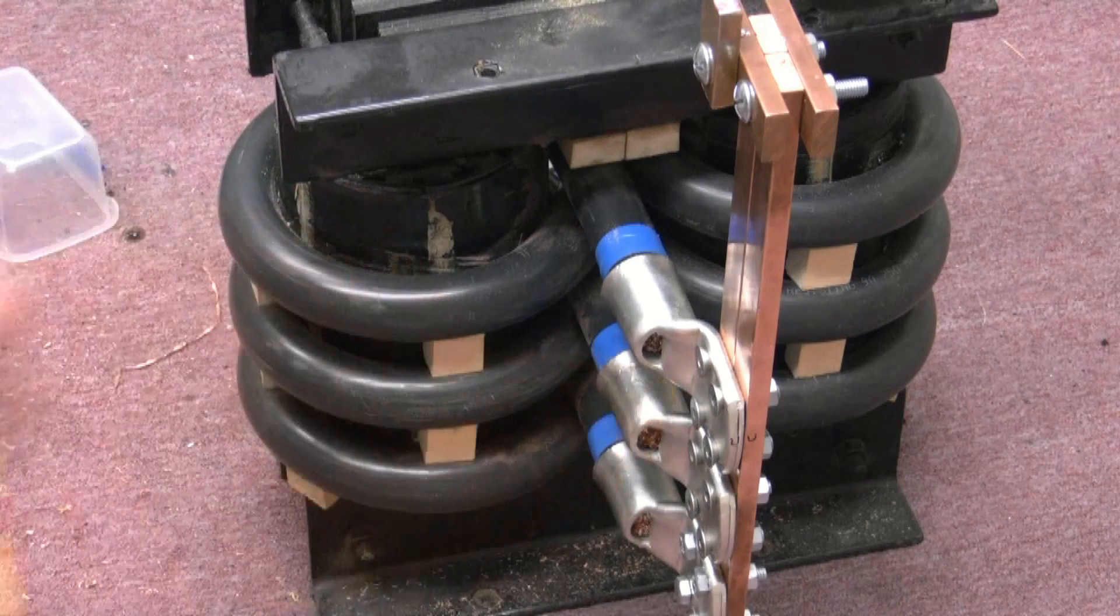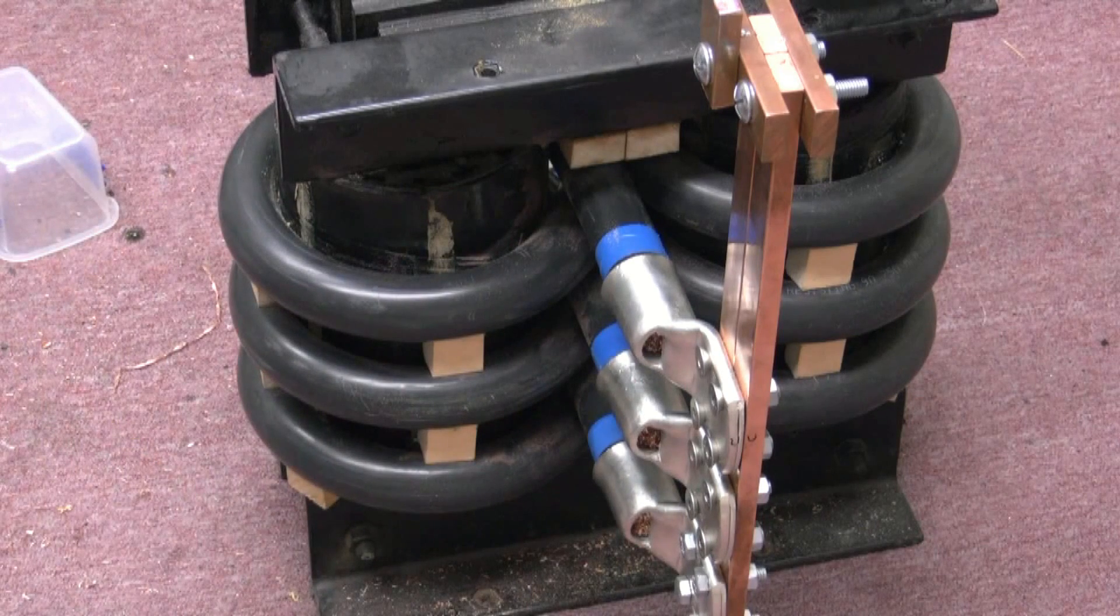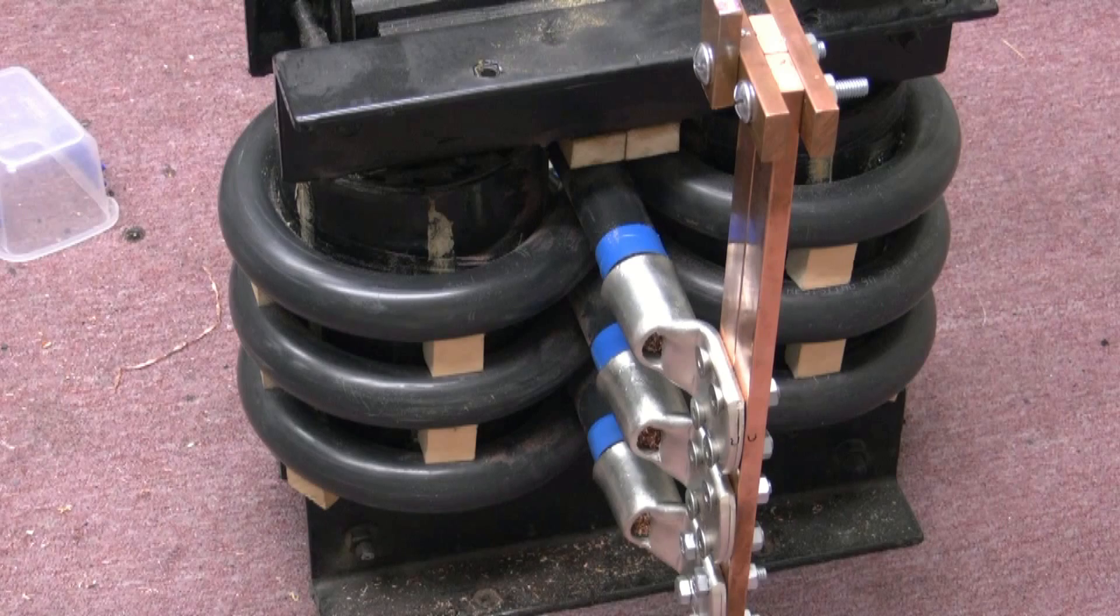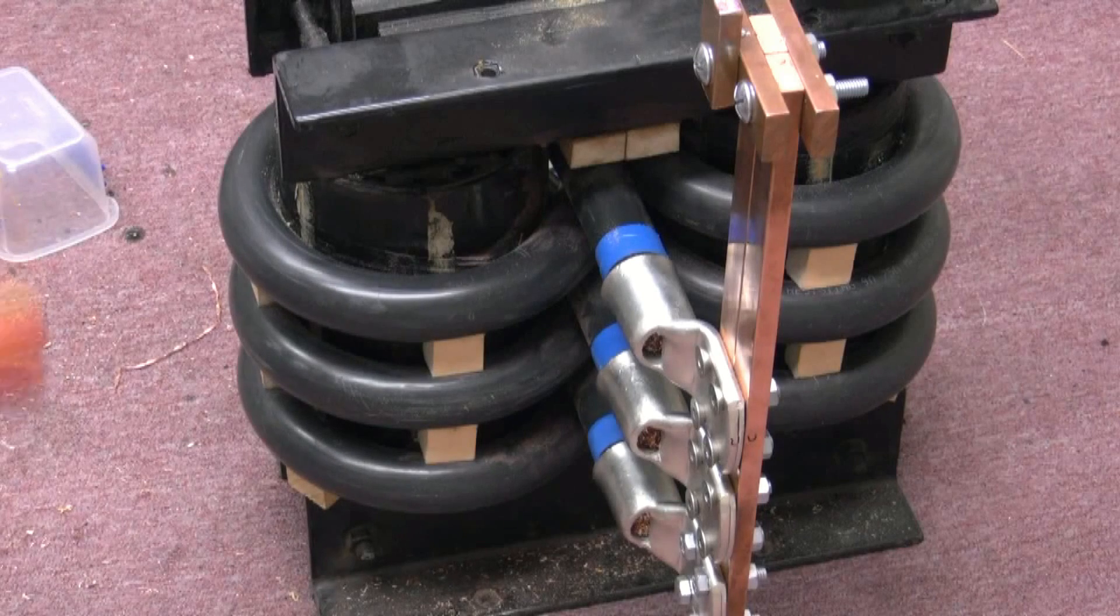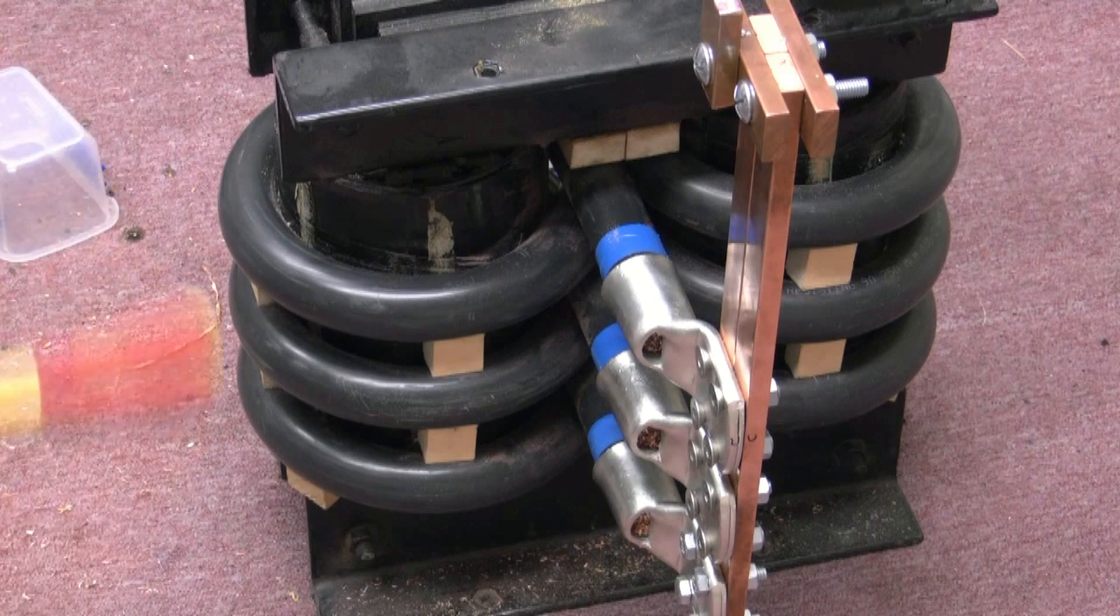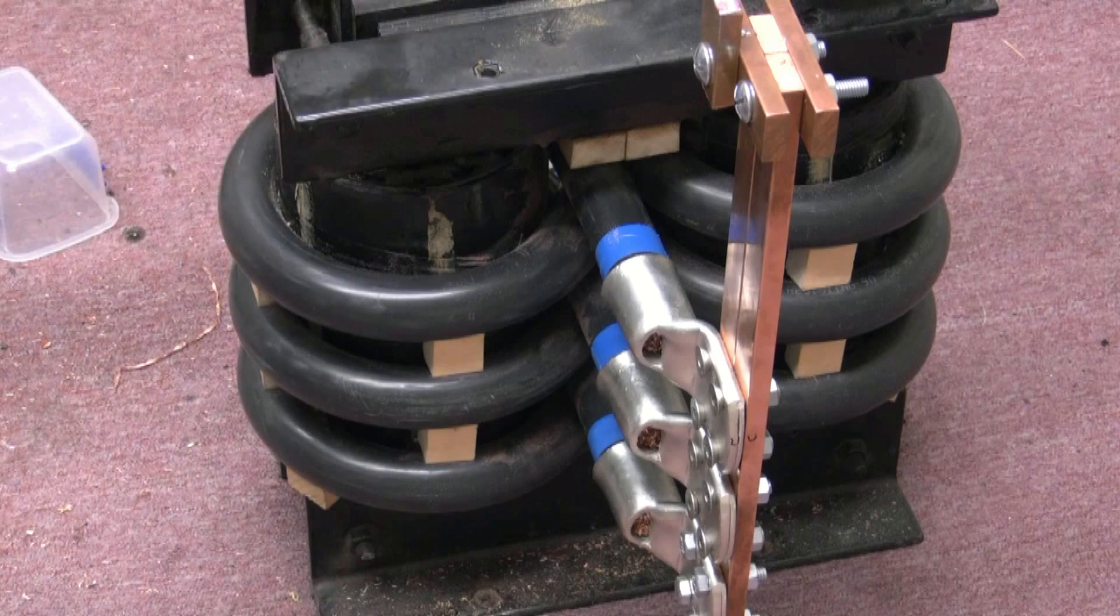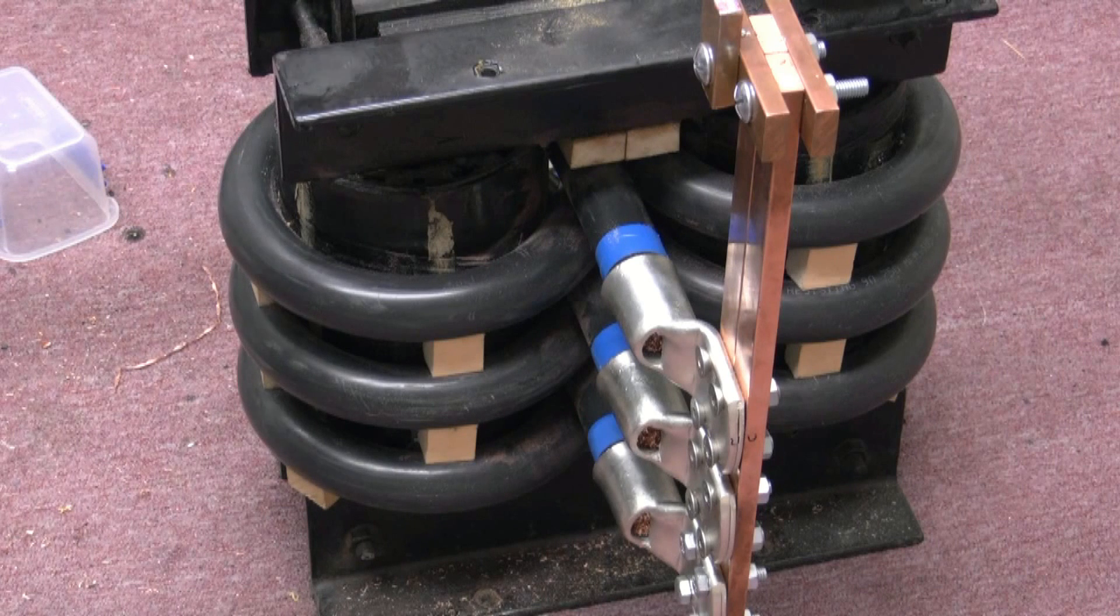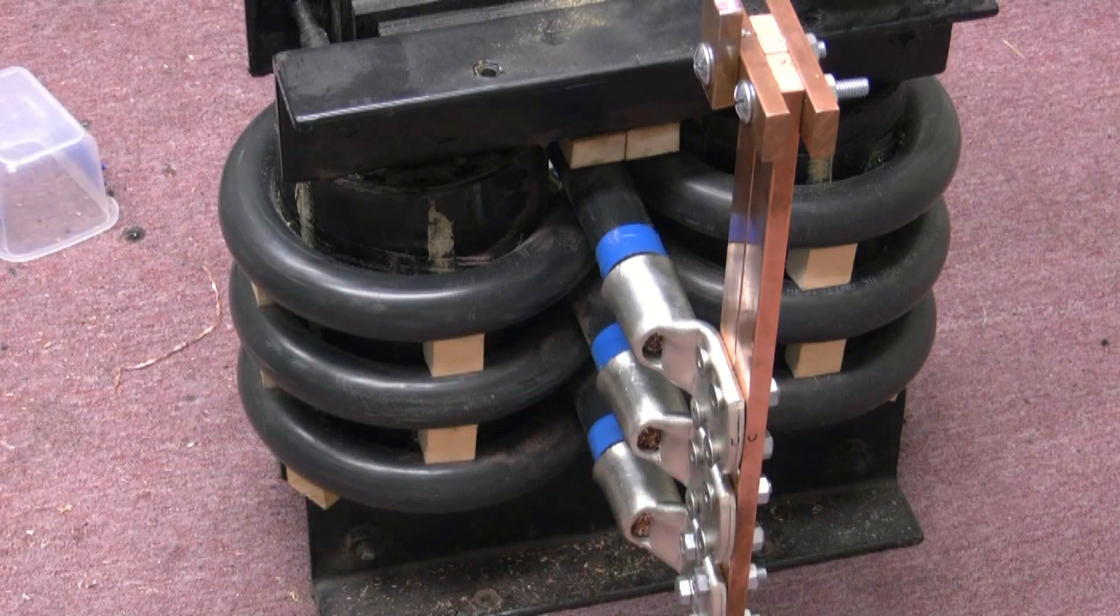And then there's three of those, all in parallel. So you've got one output there, and one on the other side. Voltage on short circuit current is probably about half a volt, and obviously off-load, probably 4 volts. So if you take half a volt, and we've got probably 15 KVA, then 30,000 amps isn't unreasonable. But if we can put 100 or possibly 200 amps into this transformer, then there's no reason why we can't have 50,000 amps or more.